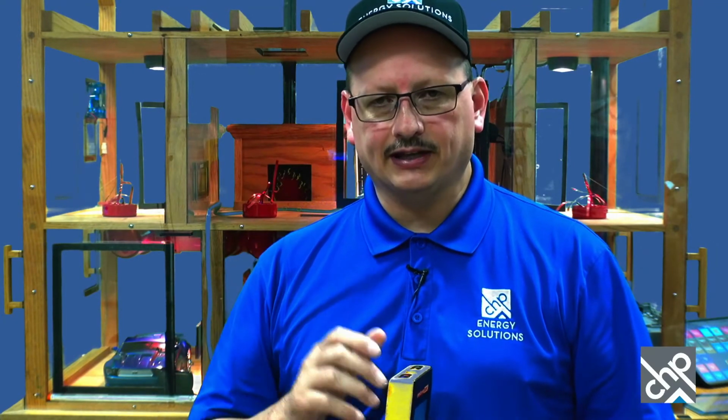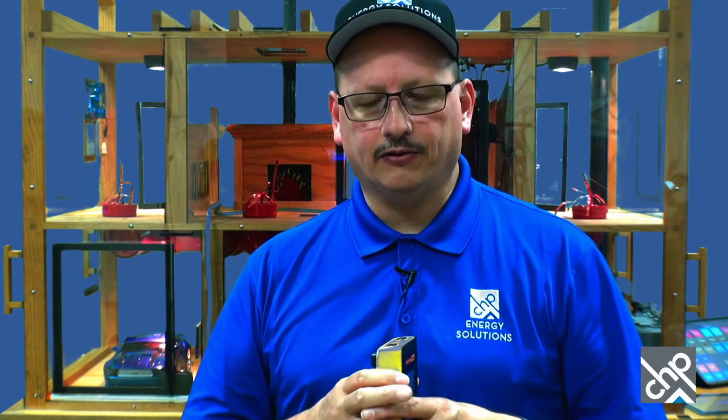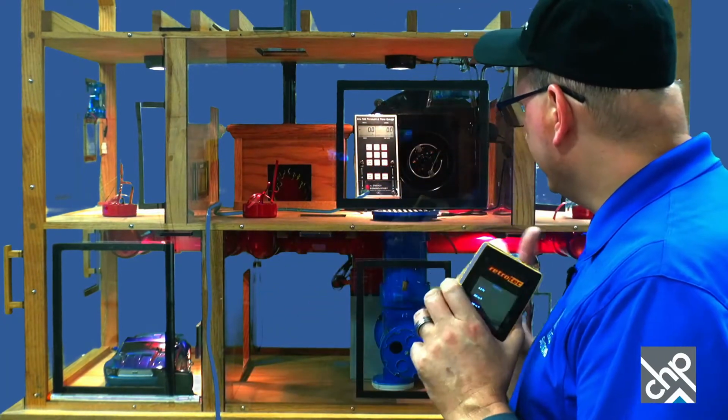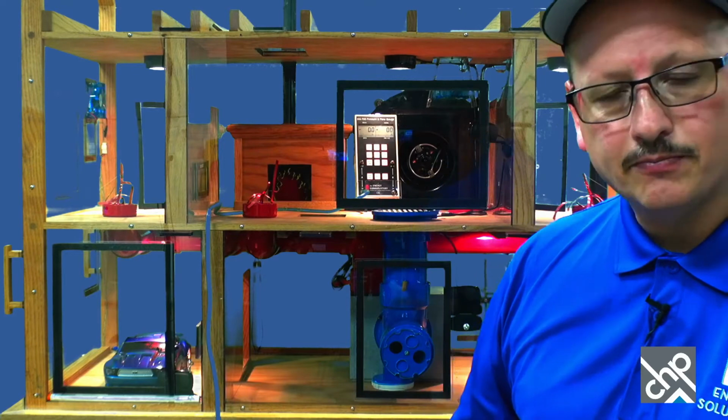And all the gauges have that. They just have different ways to get to it. I showed you on the DM32, the DG700. You've got baseline, and then you hit start, and once your 30 seconds is counted down, you hit enter. Similar on the 1000 gauge. But anytime you're measuring pressure between indoors and outdoors, and when you do that baseline, you have all your exterior windows and doors closed, all your interior doors open, and all your mechanical equipment off as well.